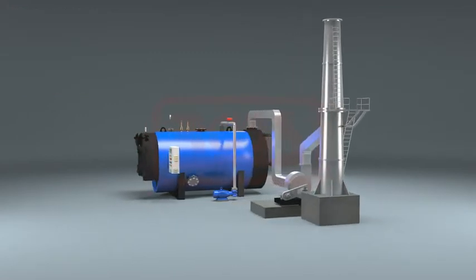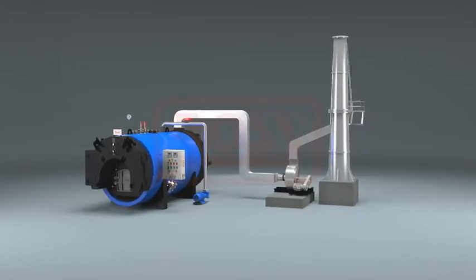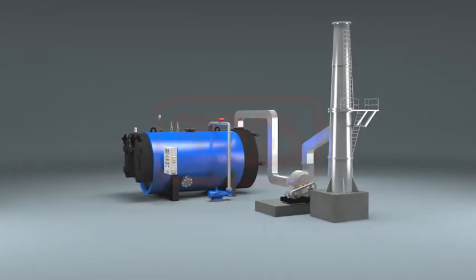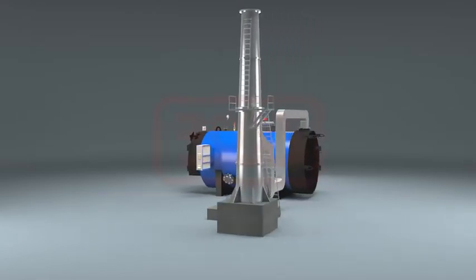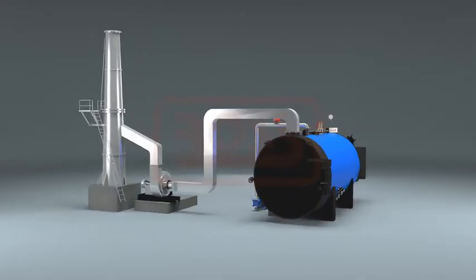The furnace, tube plates, and outer shell of the Sigma hot water generator are made of boiler quality steel plates, and the smoke tubes forming the second and third flue gas passes are made from boiler quality tubes. A refractory door is fitted on the front for fuel feeding onto the grate bars in the furnace.